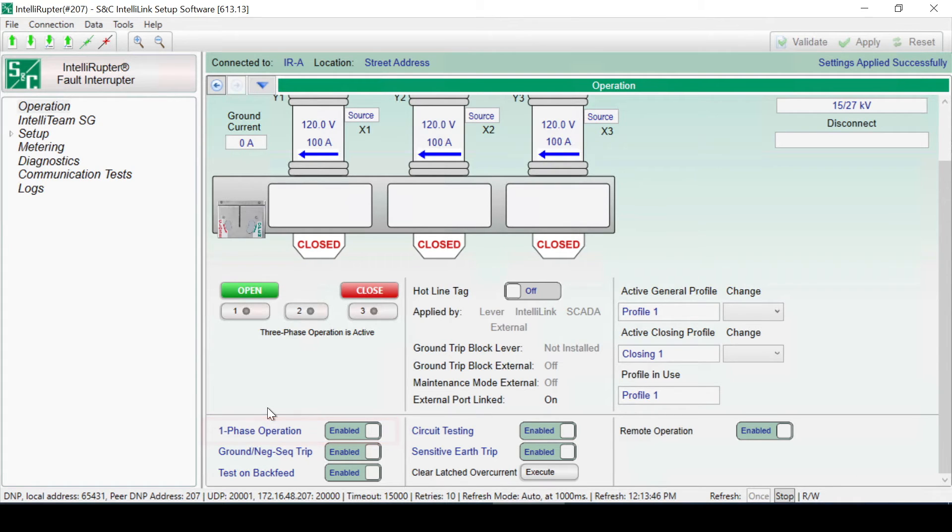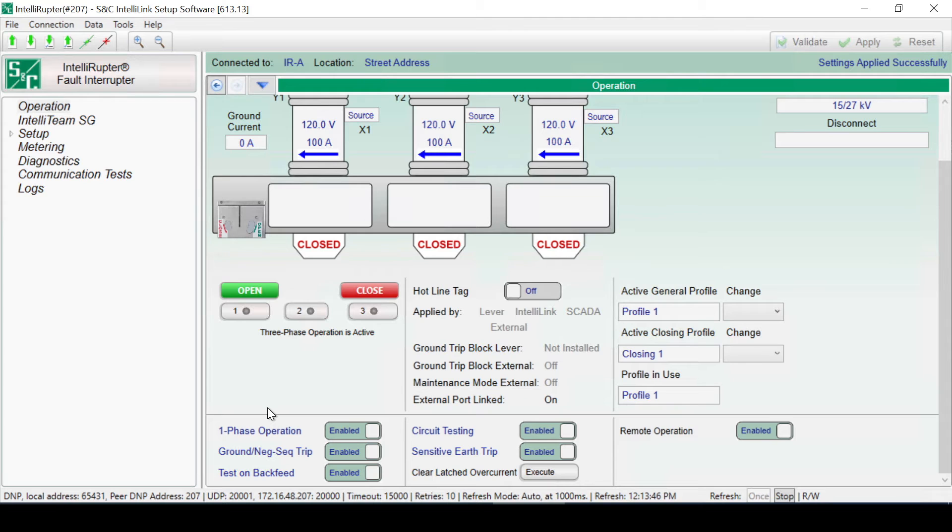There's also a one-phase operation slide control. This must be set to Enabled in order to attempt single-phase operation. If this is set to Blocked, the switch will always attempt three-phase operation.